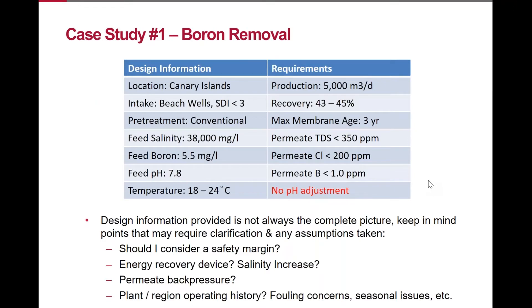The first case study we're covering is boron removal — a plant in the Canary Islands with beach wells, SDI less than three, conventional pre-treatment. Feed salinity is approximately 38,000 mg/L, 5.5 mg/L feed boron, 7.8 feed pH. Operating temperature will be between 18 to 24°C. Production is 5,000 m³/day, recovery 43 to 45%. Maximum membrane age is three years. Permeate quality requirements: TDS less than 350 ppm, chloride less than 200 ppm, and boron less than 1 ppm.